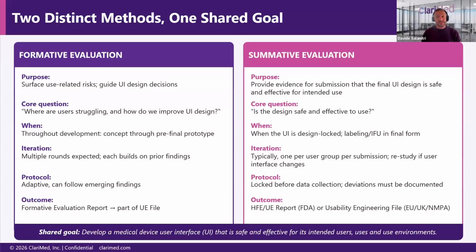Sometimes we do a formative of 2 days, change the protocol, other 2 days, change the protocol, other 2 days, and go on. Summative is a protocol that you do, you approve it, you lock it. That is what you're going to do. Every bit that you're going to change during the study, for whatever reason, will have to be justified and will have to be reported in the report. So it's very strict, it's very square, I would say.